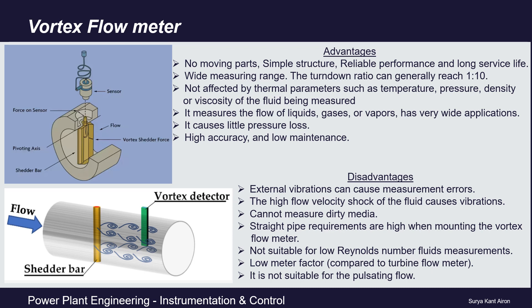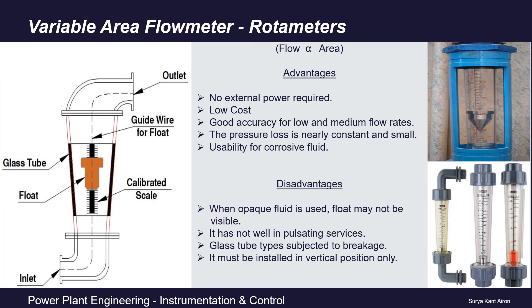The next category is variable area flow meters, which are basically rotameters. Rotameters are used to measure liquid or gas volumetric flow rate as it passes through a tapered tube. Fluid enters through the bottom inlet, exerting pressure on the float, causing it to rise. As the float rises, the cross-sectional area of the tapered tube increases, and since flow is directly proportional to area, the float position is calibrated to give flow indication.